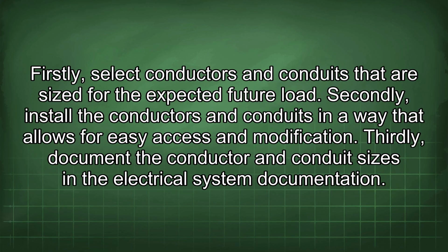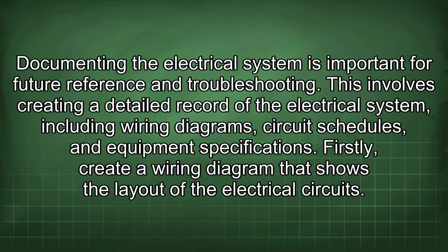Firstly, select conductors and conduits that are sized for the expected future load. Secondly, install the conductors and conduits in a way that allows for easy access and modification. Thirdly, document the conductor and conduit sizes in the electrical system documentation. Documenting the electrical system is important for future reference and troubleshooting. This involves creating a detailed record of the electrical system, including wiring diagrams, circuit schedules, and equipment specifications.